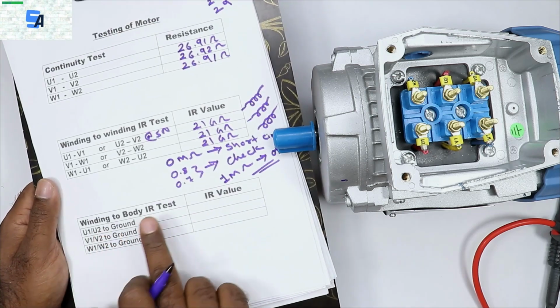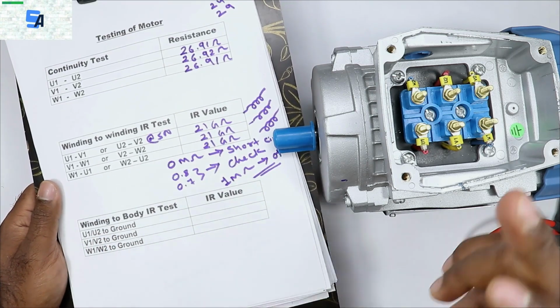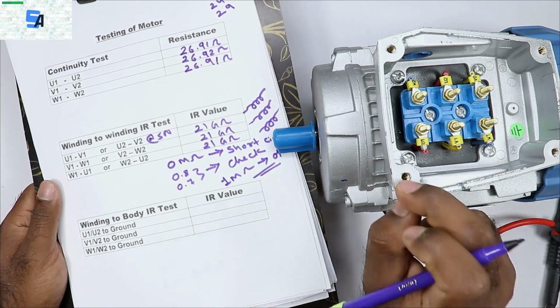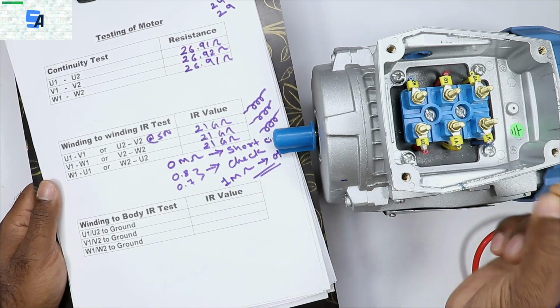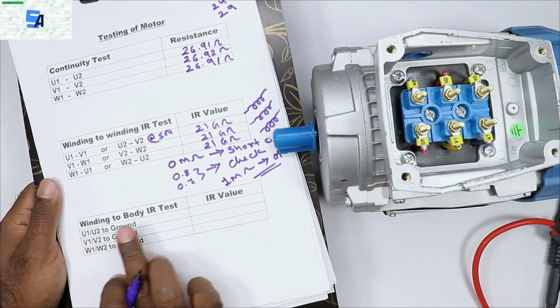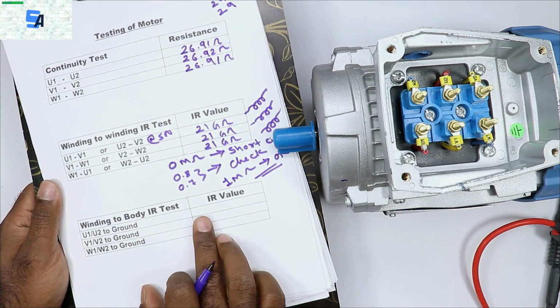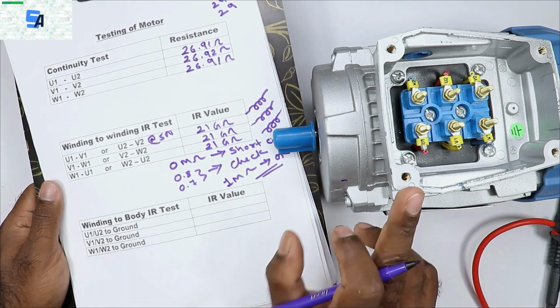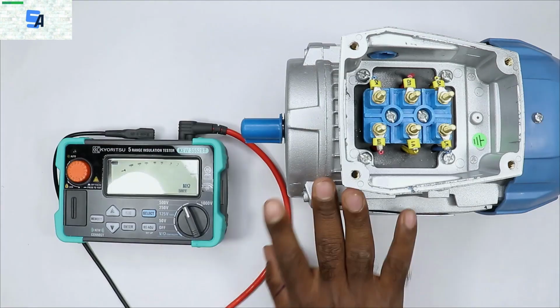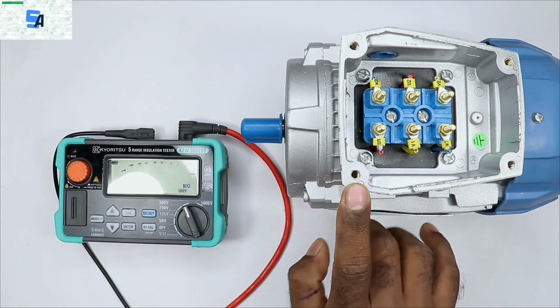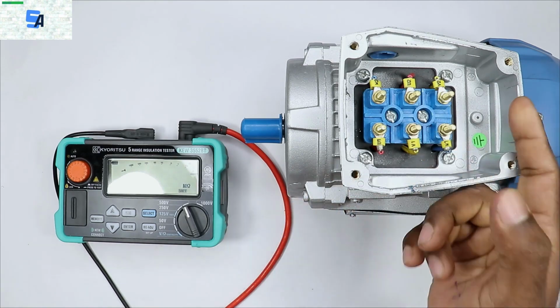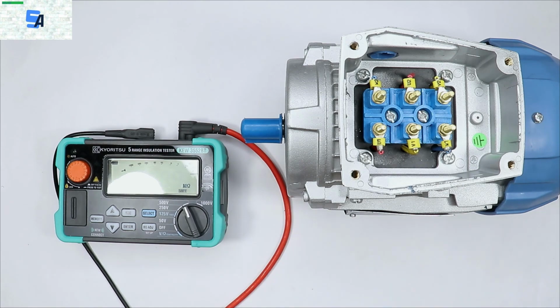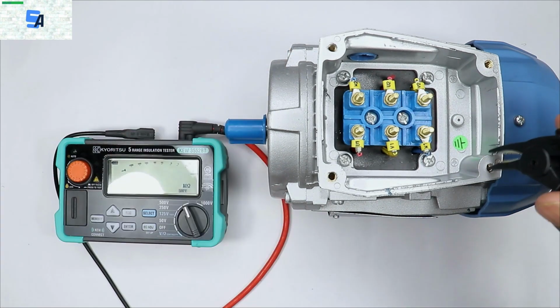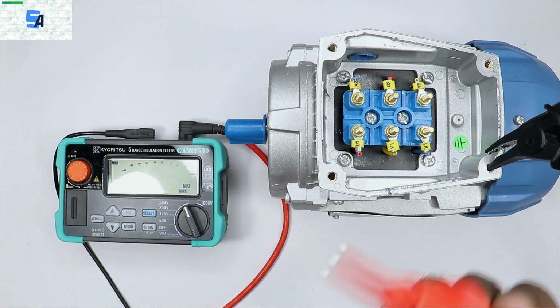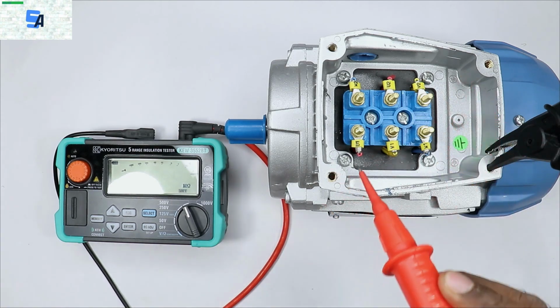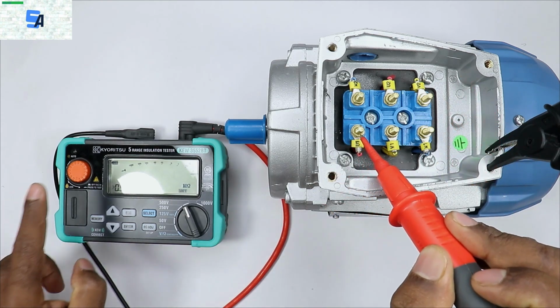Now we have to do the winding to body IR test. It means that if a winding of the motor is connected with the body of the motor by mistake, to check this we need to do the winding to body IR test. For this, we will check all 3 windings against the body of the motor, to see how much insulation resistance there is between them. To measure this, connect one probe of the Megger with the body of the motor. After this, take the second probe and connect it with U2. After connecting this, press the test button.